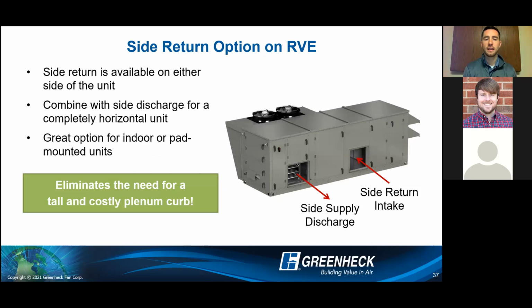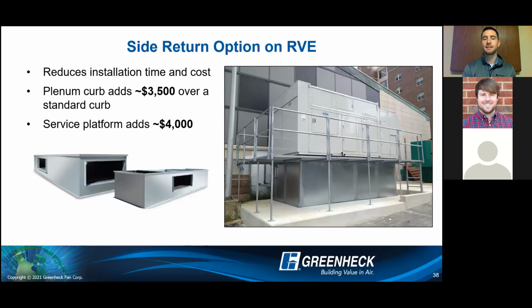Another nice advantage we have on the RVE and RV product line is horizontal connections. So with all the redesigns that we did and the new housings we rolled out, now from 3 to 70 tons on all the housings, you should be able to get horizontal connections. What's nice about that is it eliminates the need for a tall, costly plenum curb. So if you want to mount it on a smaller curb, if you want to mount it on a pad or indoors, it gives you the ability to do that with those full horizontal connections, which means it doesn't have to look like this, right? We want to reduce the installation time and cost that you guys are seeing out there. A plenum curb adds about $3,500 over a standard curb. And then if it requires a service platform because it's too high, that's about another $4,000. So definitely want to utilize it to your advantage with those full horizontal connections in the RVE product line.